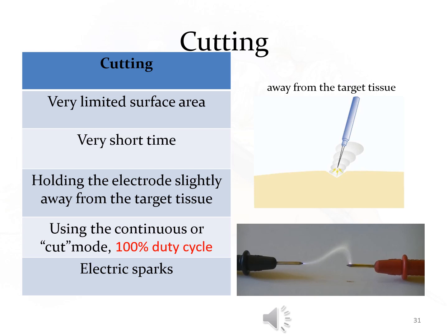By sparking to tissue, the surgeon produces maximum current concentration. To create this spark, the surgeon should hold the electrode slightly away from the tissue. This will produce the greatest amount of heat over a very short period of time, which results in vaporization of the intracellular contents of the tissue.